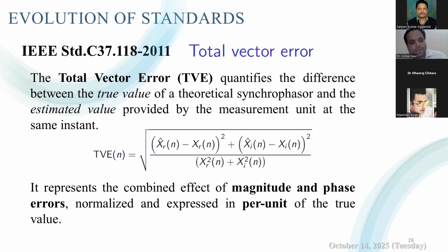This IEEE standard also defines the error metrics to evaluate the accuracy of synchrophasor measurements. The most important of these is the total vector error, or TVE. TVE essentially compares the true theoretical phasor with the estimated phasor reported by the PMU at the same instant. So it combines both magnitude as well as phase error into a single measure.